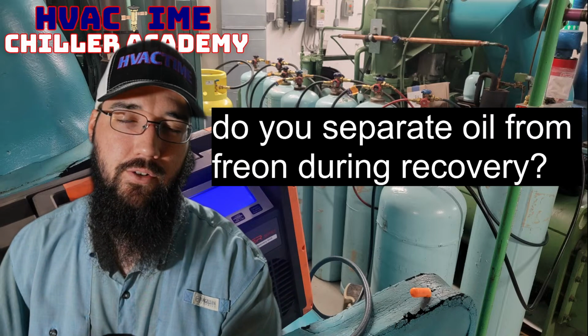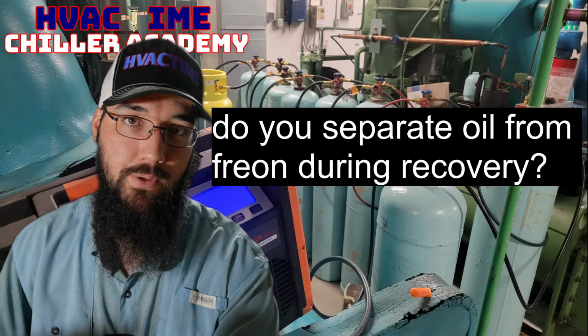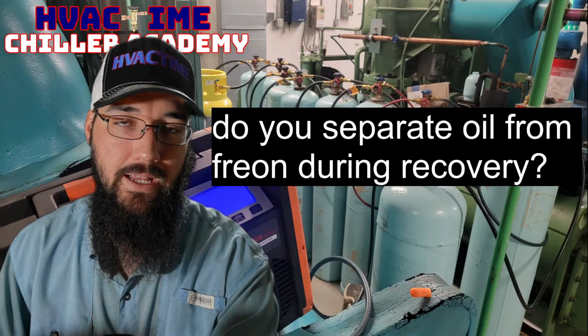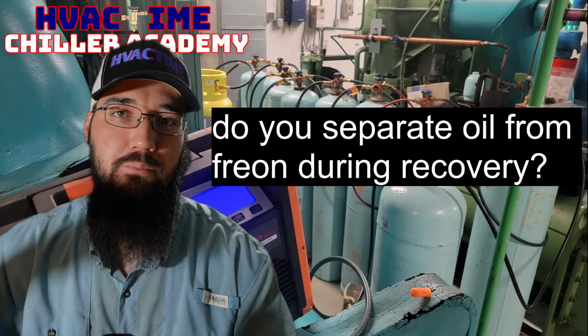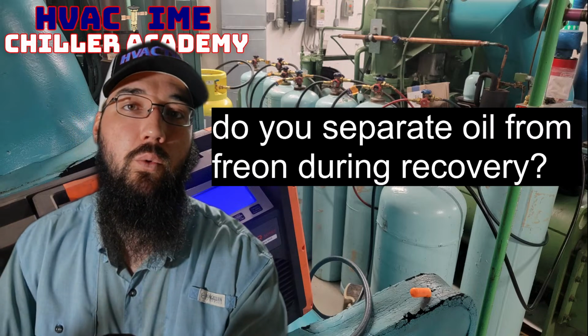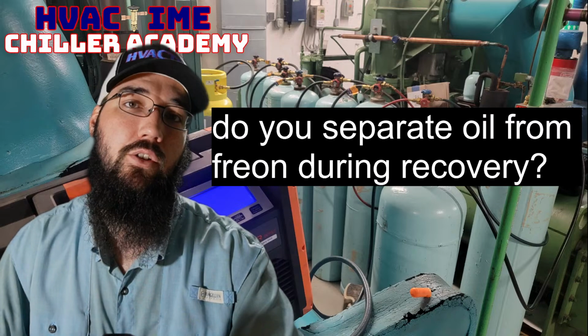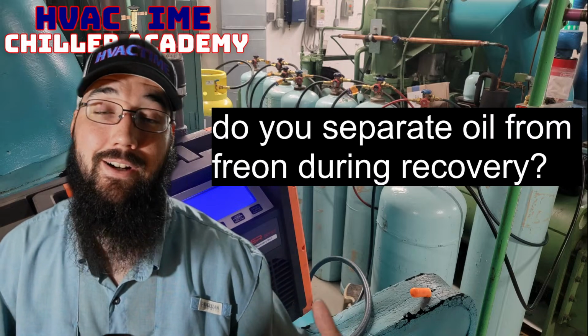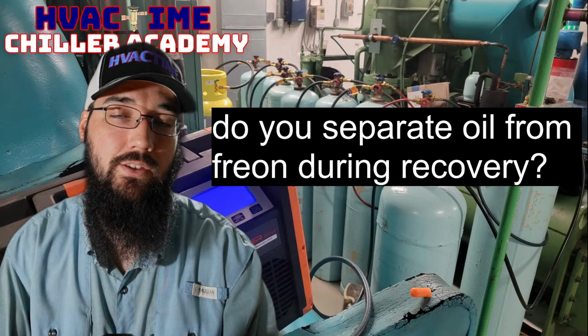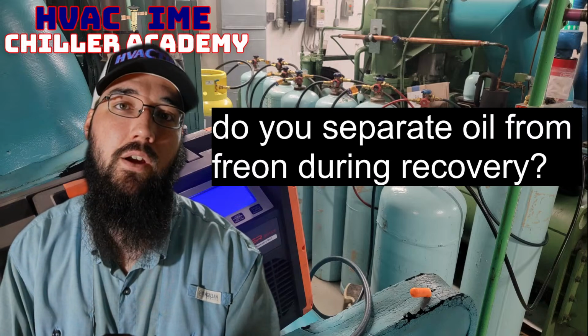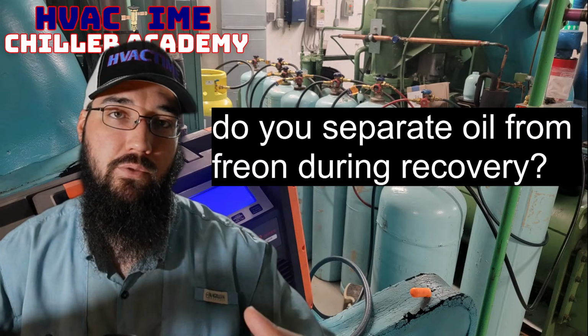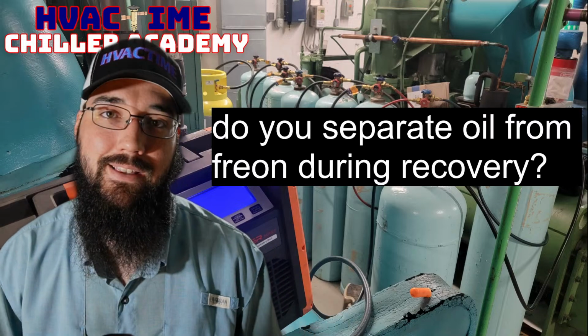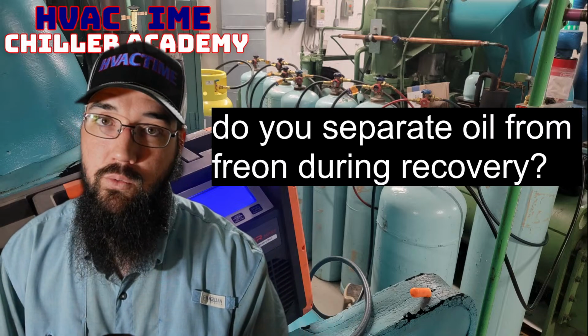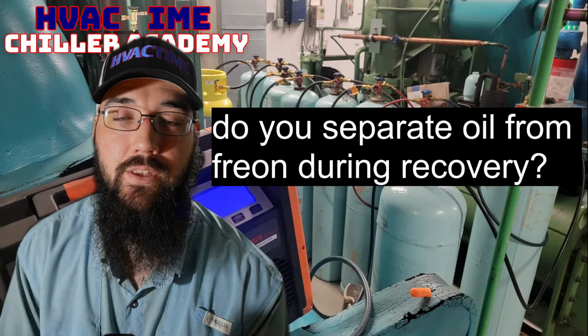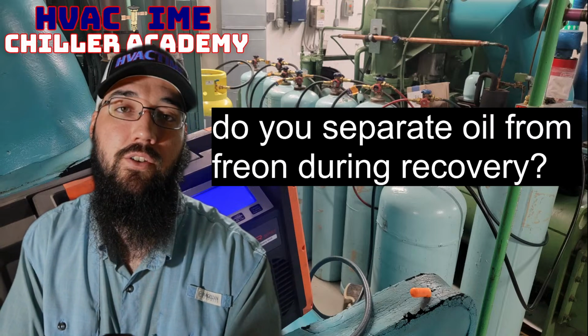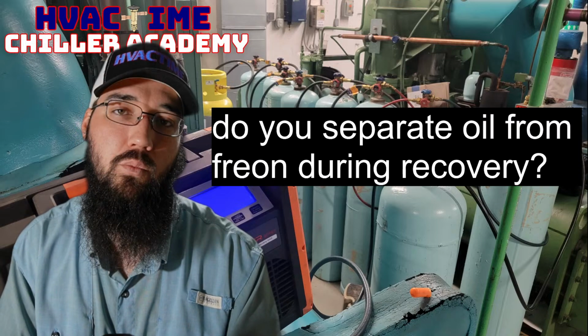But that last cylinder that everything got stacked into should be your oil laden cylinder. The only way to get those two apart from each other is to flash that refrigerant out of there, and it takes a long time. It's a very slow process. Tank heaters and things like that will help speed that process up, get that refrigerant to flash faster. What that leaves you with is all of that oil that stays in the cylinder. It's got to be dealt with in some way at that point.